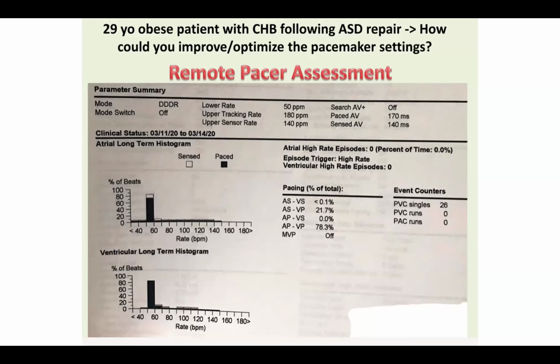Now, interestingly, maybe next week we'll go over this, but even though it says that the upper tracking rate is 180, if the post-ventricular atrial refractory period setting is too long, and if the PR interval or the AV delay you've programmed is too long, then the patient may not actually track that high. In the bedside pacemakers, you can actually set the tracking rate, and the device will automatically adjust the AV interval and the post-ventricular atrial refractory period to be able to track to that. But in a permanent pacemaker, it's the responsibility of the electrophysiologist to calculate whether it will actually track that high. Because even though the device will allow us to program it that way, if the math doesn't work, it won't track that high.